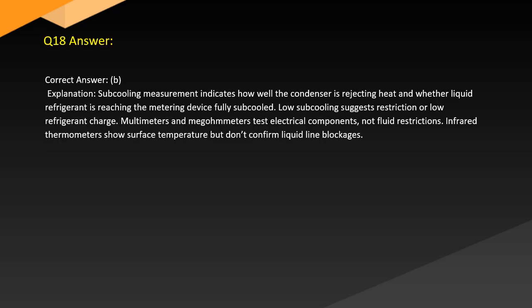Answer. Correct answer, B. Explanation. Subcooling measurement indicates how well the condenser is rejecting heat and whether liquid refrigerant is reaching the metering device fully subcooled. Low subcooling suggests restriction or low refrigerant charge. Multimeters and megohmmeters test electrical components, not fluid restrictions. Infrared thermometers show surface temperature but don't confirm liquid line blockages.